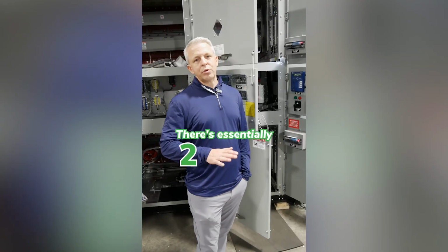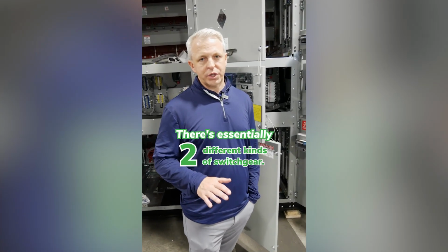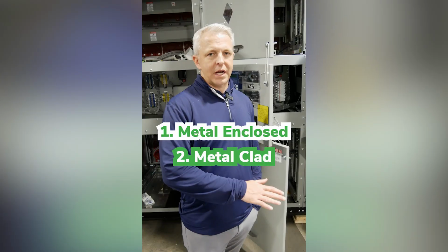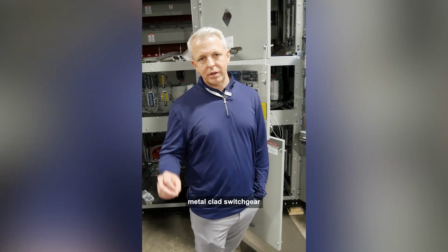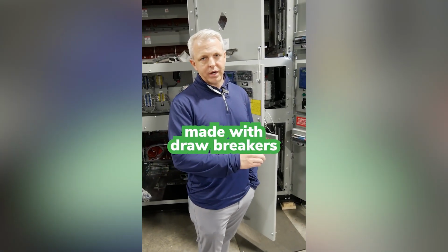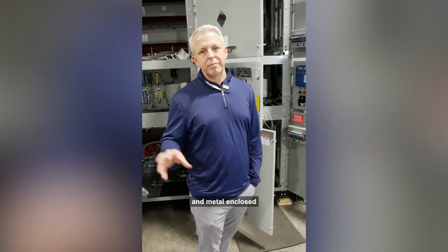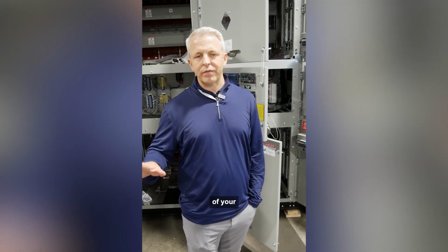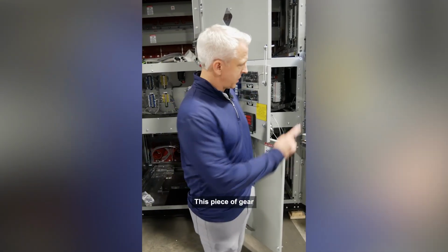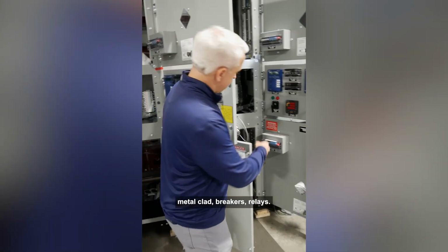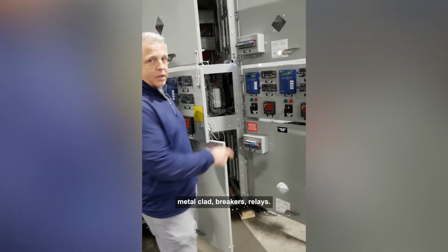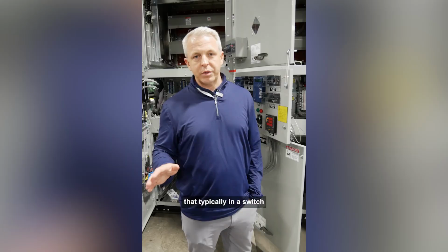There are essentially two different kinds of switchgear: metal-enclosed switchgear and metal-clad switchgear. Typically, metal-clad switchgear is made with draw-out breakers, and metal-enclosed switchgear is more of your switch and fuse type of gear. This piece of gear right here is metal-clad. Breakers, relays. You're not going to see that typically in a switch and fuse lineup.